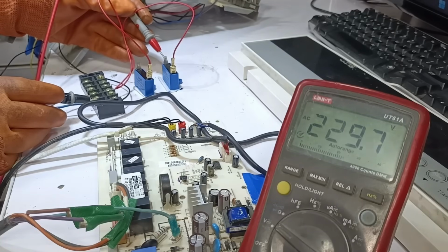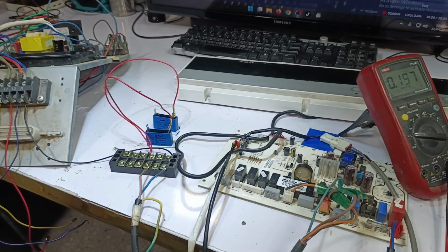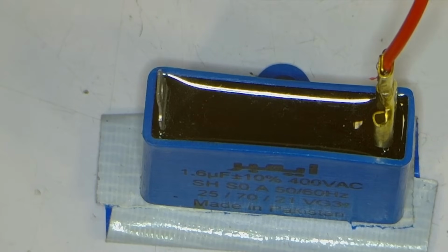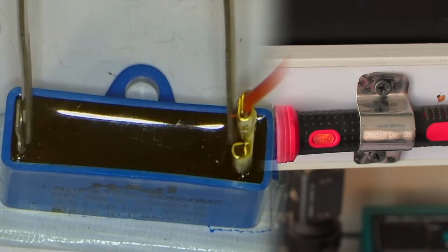Here too, we are getting 229 volts AC. This means all 3 phases are properly working. Now, I will switch off the power. We will discharge both capacitors. If there is any stored charge in them, it will be released. We will also discharge the second capacitor. Now, there is no charge remaining in either of the capacitors.